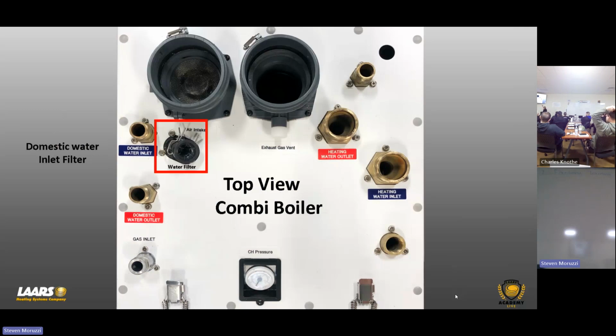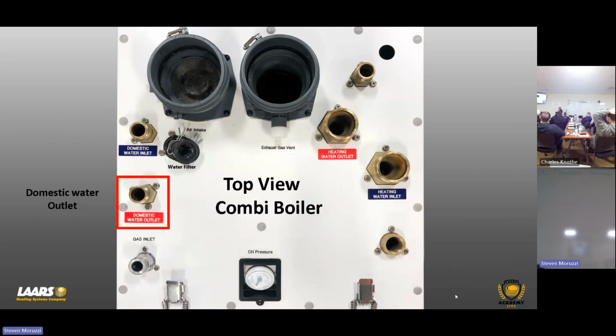We even give you the hex fittings for the heating pipes and domestic water in and out, okay? Why? Because a lot of times you'll have guys putting those fittings in, they're cranking down with an 18-inch or 12-inch pipe wrench. What are you doing? You're twisting that pipe down inside that cabinet. So now you can back that up with a wrench, all right? And that way you're not twisting the pipe, and they're also screwed in, all right? So again, it's a weather-tight cabinet, if you will. So we do have that screen or strainer for the filter, and then we have the domestic hot water out.